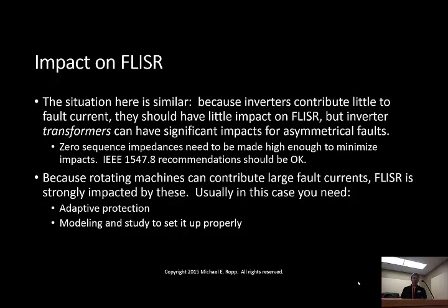What the situation is here is it's one of those cases where I've got a normally open tie to a second source. And of course, we do this all the time in distribution, right? I'll take a part of a circuit and switch it over to another source. All FLISR is doing is automating that process. I'll have a set of relays that are talking to each other on the feeder. Then if a fault occurs, the relay that is upstream but closest to the fault should be the one that opens because I've got them coordinated.